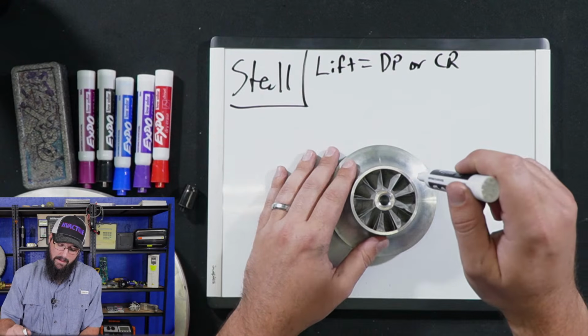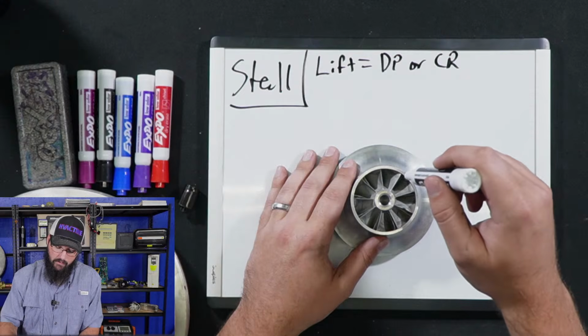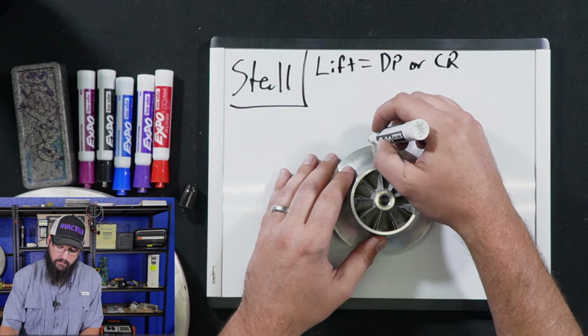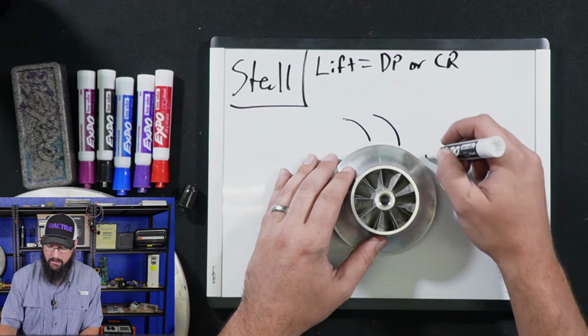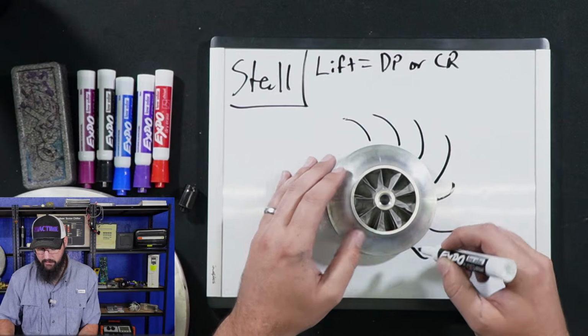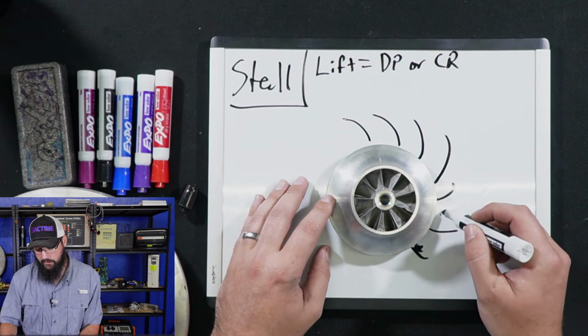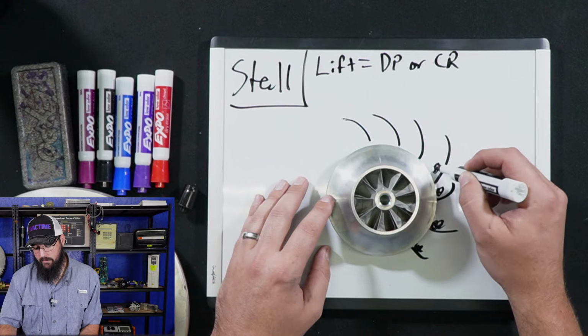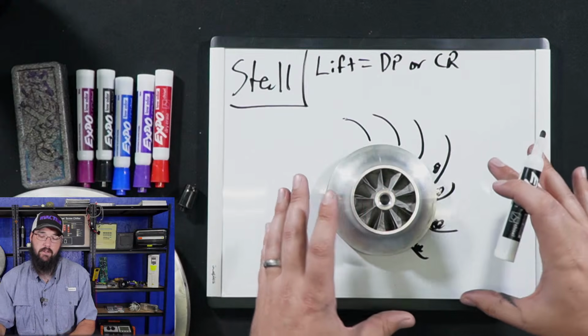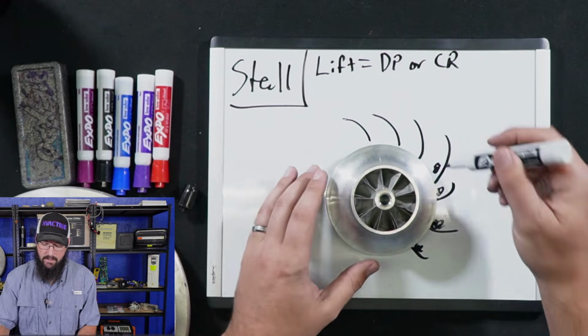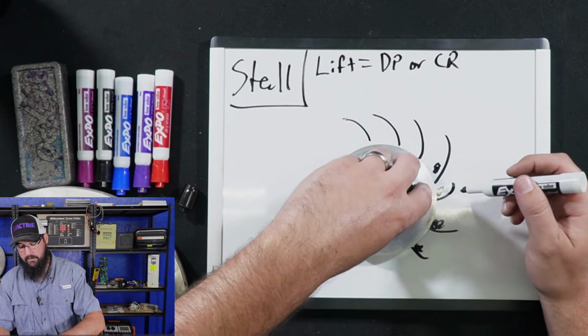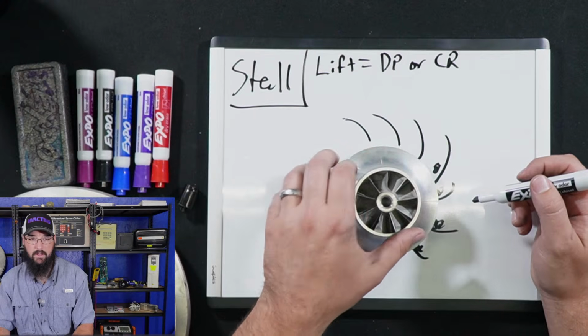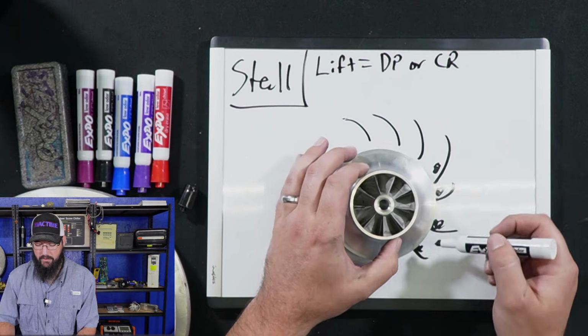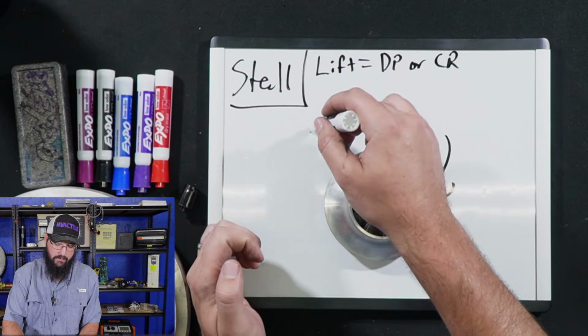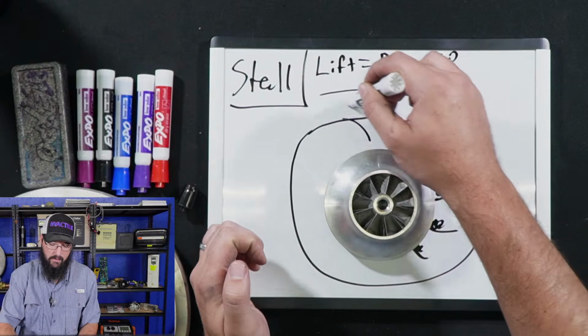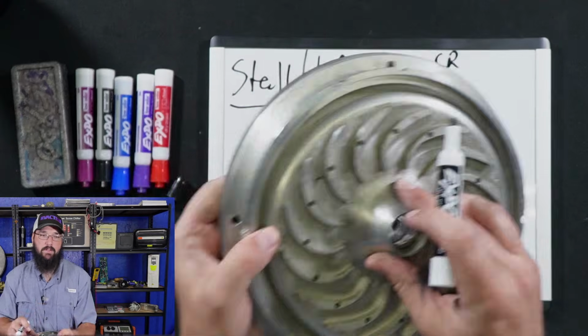So we start running high lift. We get to where the refrigerant coming out of the impeller starts to struggle, and we get these little eddy current zones where it just can't fully push through because of the built-up differential. What ends up happening is this is referred to as a rotating stall. So as the impeller is spinning, if we're stalling right here in this zone of the volute, the volute is the housing that wraps around this right here, could be considered like the type of volute.